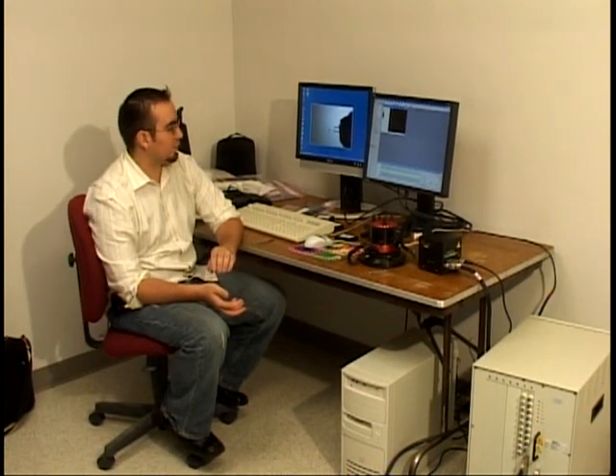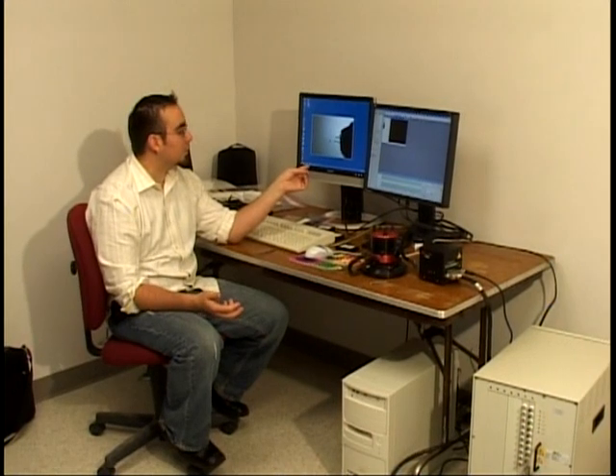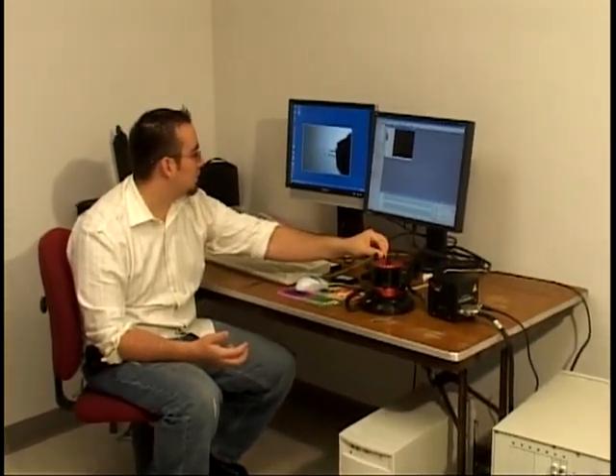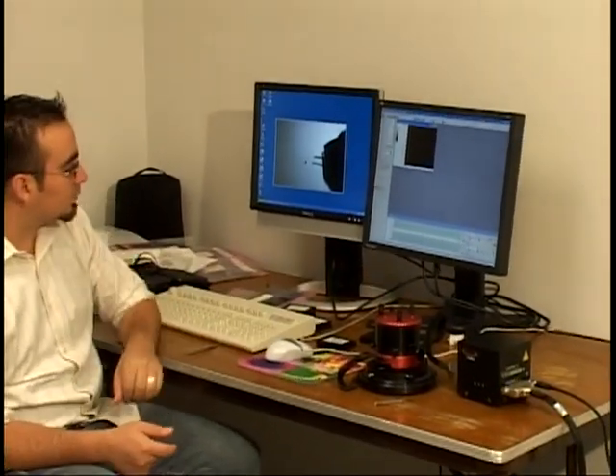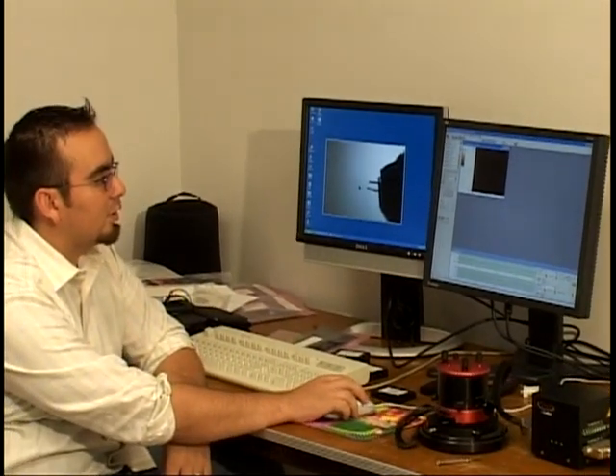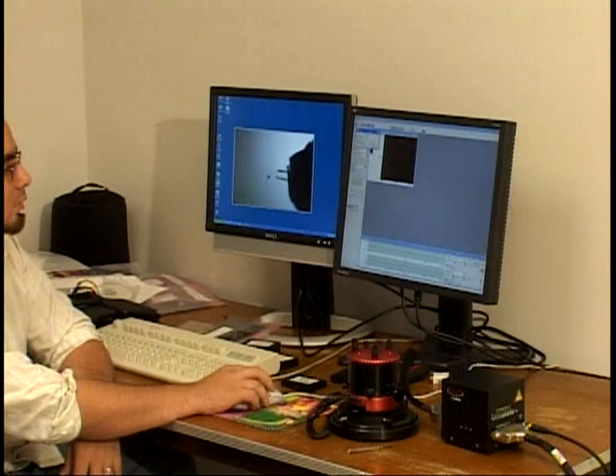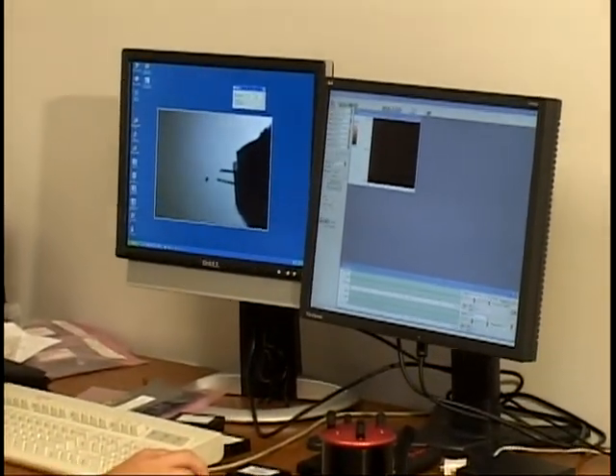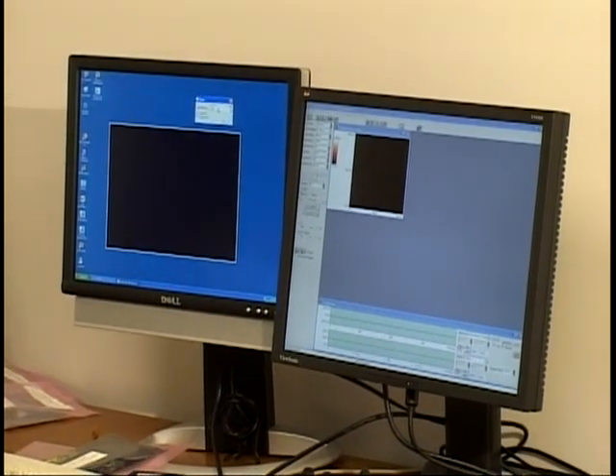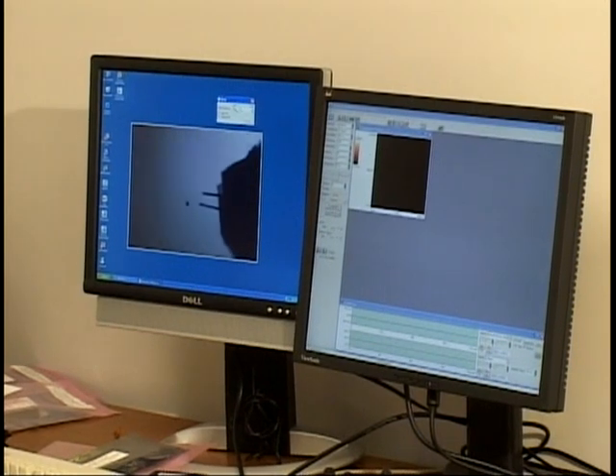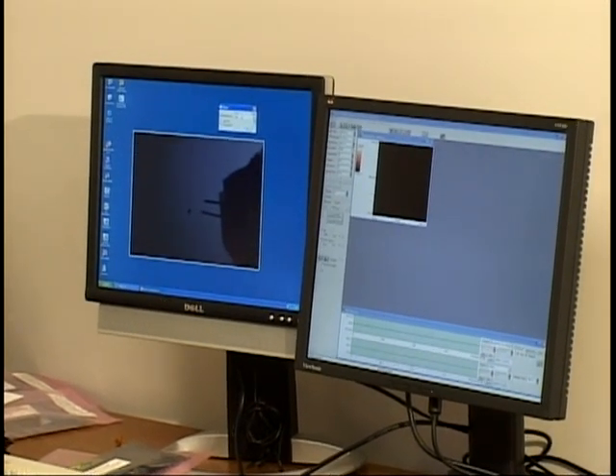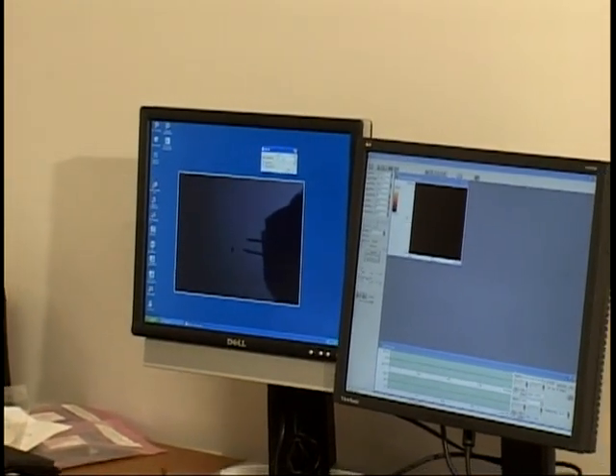First thing we're gonna do, basics of just getting into contact mode. So we want to be able to put the laser on the probe and then line it up until we get it right in the middle. I'm gonna go through the steps. First thing we want to do is focus the probe as sharply as we can using the top knob. And that's pretty good right there. After that, we should go into the setup video window. Go to setup video. And you can adjust the intensity of the light so it's not too dark that we can't see anything, but dark enough to be able to see the laser. So right now we can't see anything because we haven't turned it on.